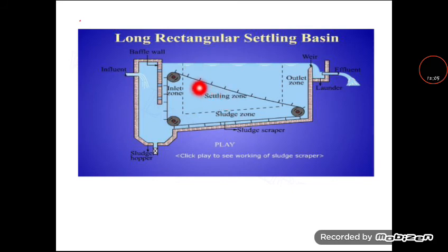available inside the tank. So to avoid the shocking load of the water coming into the settling tank, we provide the baffle walls. These are vertical walls provided at the inlet and outlet. What is the use of baffle walls in the outlet? It is to prevent the particles from escaping. So we use the baffle walls in the outlet also. After that, the water which is stagnant in the tank flows through the baffle wall, and may be brought to the next unit operation.